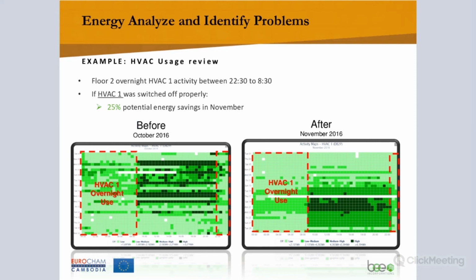Here again we see this HVAC overuse at night, and visually how it shows up in this graph. The dark green dots are the hours where most electricity is used. You can see in the left graph that during night time, marked in red, there's light-colored HVAC use, but still some darker spots. Analyzing this monthly chart shows some AC units are not switched off properly, and in this case we identified a 25% saving potential in one month for HVAC electricity use.